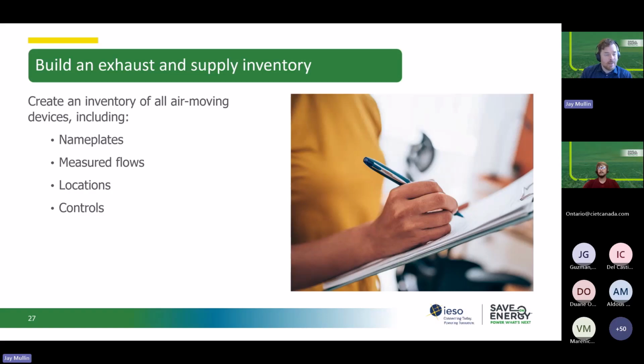On the supply side, again, you want to make sure you're capturing all the makeup air units, obviously, but also rooftop units or air handling units that have an outdoor air intake component. Not their total supply, but you want to know that outside air component. If you have any dedicated outdoor air systems, but also some things that are commonly missed, things like compressed air that might be bringing air in from outside the facility, purge air, relief air paths. Depending on how large a role or the size of these systems in your facility, those can have a material impact on that air supply side of things.